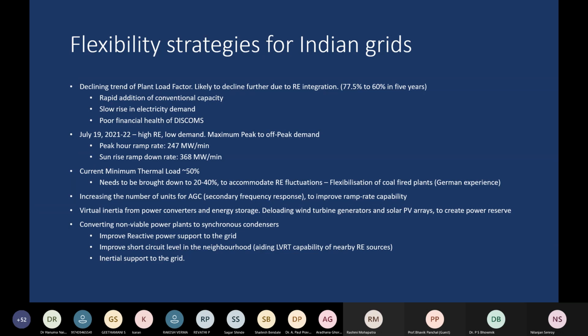So deloading means that the blades of the wind turbine are pitched away from the wind, thereby wasting some of the wind purposefully. So the output of that wind turbine drops from 5 megawatts to maybe 4.5 megawatts, thereby creating a reserve of 500 kilowatts. So therefore you have a 10% reserve.